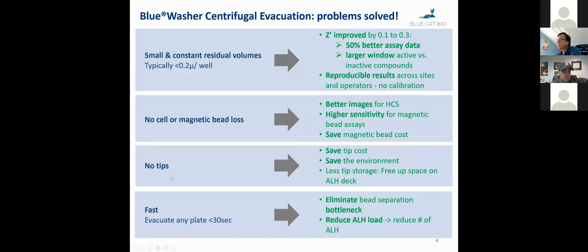So first off, we have small and consistent residual volumes, typically smaller than 0.1 microliters per well, which means that the Z prime, which is a measure for assay data quality, improves. Data becomes a lot more reproducible, and you don't need to calibrate. You eliminate cell or magnetic bead loss, which means you get better images for screening, you get higher sensitivity for magnetic bead assays, and you save magnetic bead cost because you don't have to overcompensate for anticipated magnetic bead loss by putting in more to begin with.